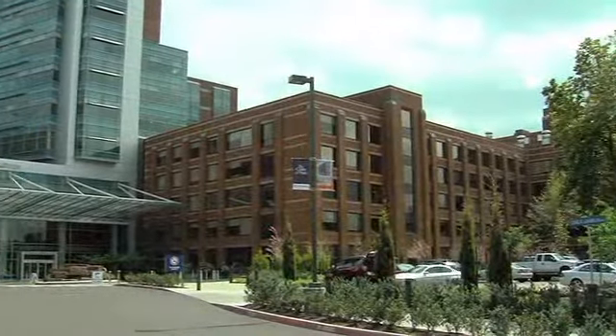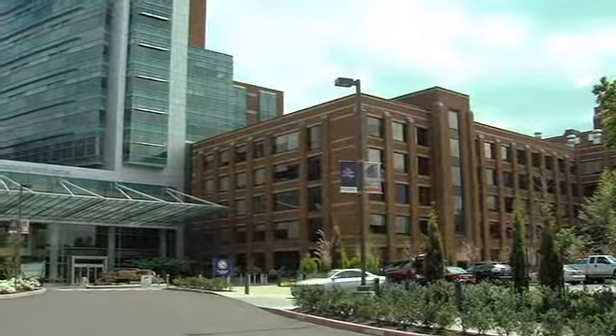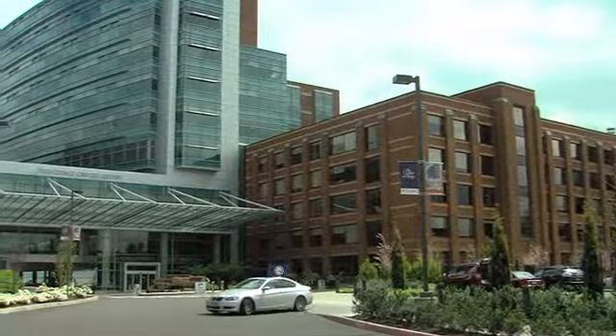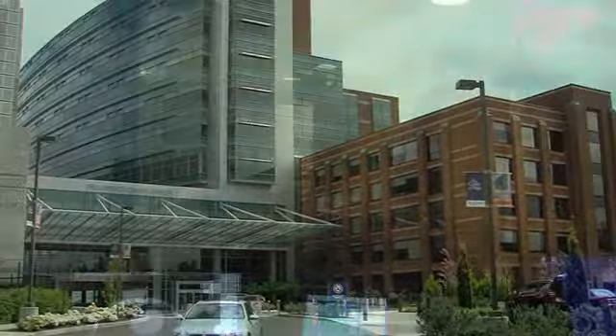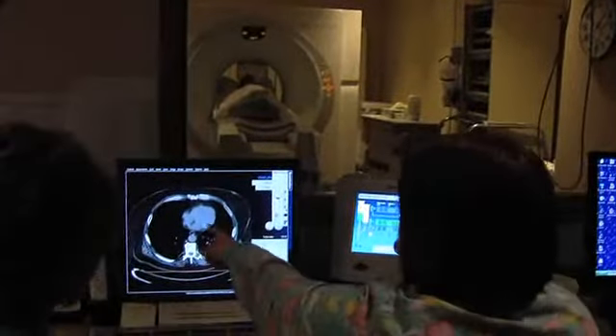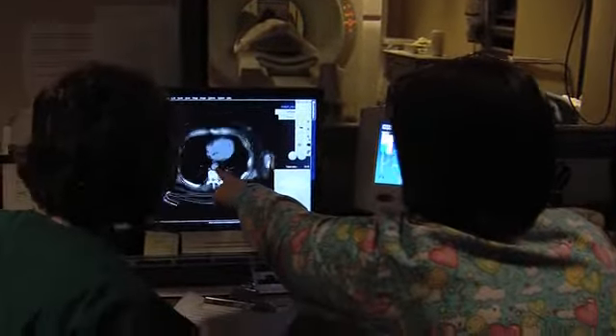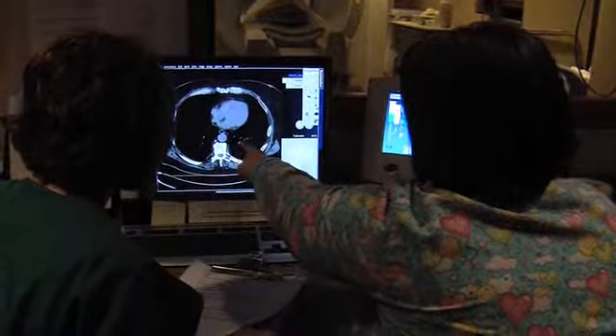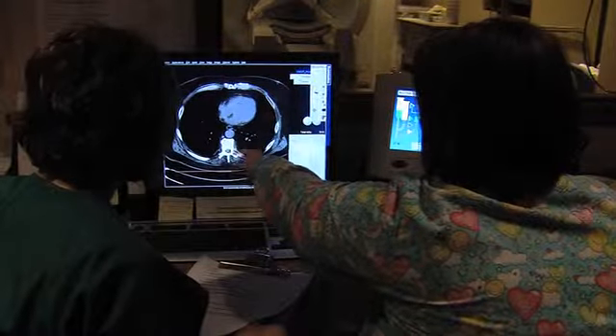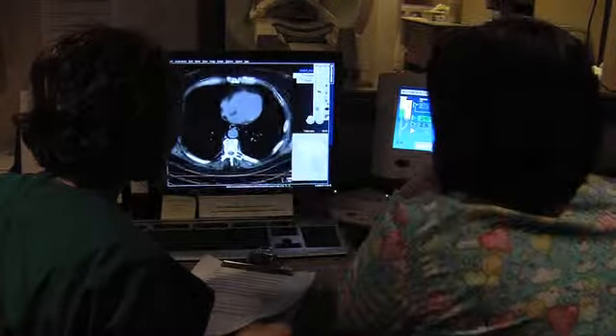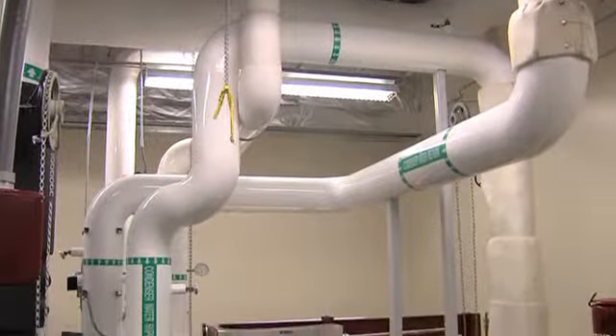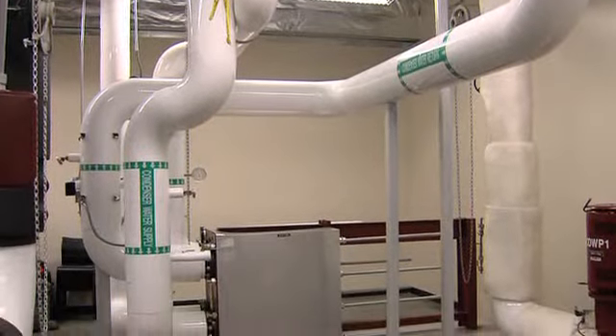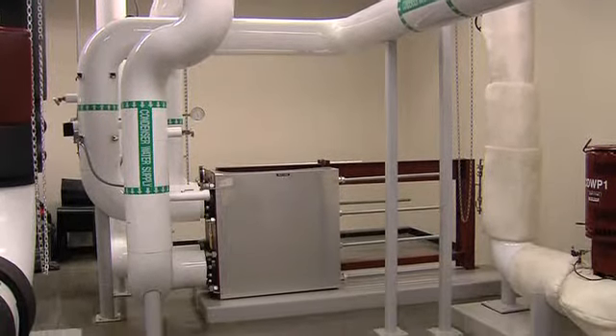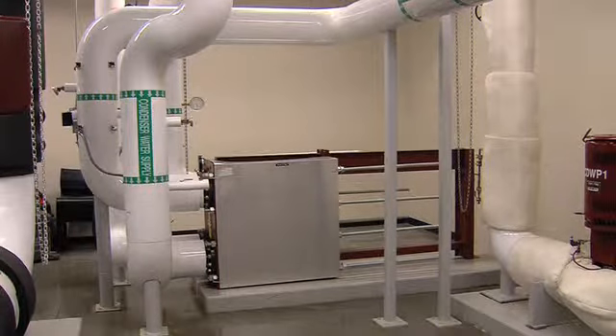2 of our chillers are on a VFD, so you can run the motor at a slower rate. On a day like today, it's about 52 to 55 degrees outside, and we're putting out about 150 tons of cooling to the hospital right now. The MRI area with the equipment rooms needs to be kept about 67 degrees, and a couple other areas in the hospital need to be kept at a low temperature. We're able to accomplish that by using outside air coming into the main hospital for keeping the building cool, and then also that little bit of chilled water that's needed for those other areas. If we didn't have that heat exchanger, we'd be running a chiller, just wasting energy.